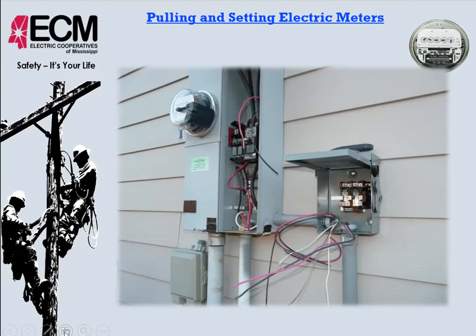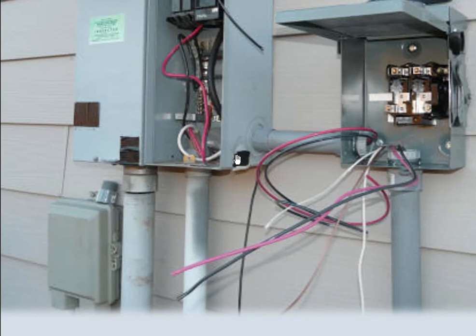But one of the things I want to point out about this picture as well is you'll notice that right here, it looks like they knocked the wrong knockout at first. So I know that tape probably accomplishes some of our concerns there, but definitely that's not a permanent fix. Not sure about the tape here and here, but that's not going to stay there. And if that were open, a kid could stick something that was metal, a coat hanger, a piece of wire in here and become electrocuted. Definitely if that comes off, wasps can build up in there, and that's something that we want to avoid.